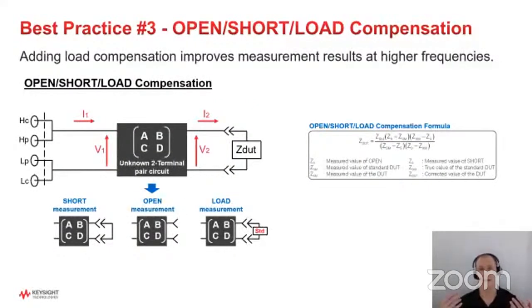Now, depending on the frequencies you want to measure at, you may also need to do a load compensation. Typically, if you're only going up to about a megahertz in frequency with your capacitance meter, and again, remember the megahertz means that's the sine wave that you're putting into the DUT, measuring magnitude and phase change. But if the frequency of that little sine wave you're putting into your DUT goes above a megahertz, then you actually can get some additional error unless you do what's called a load compensation.